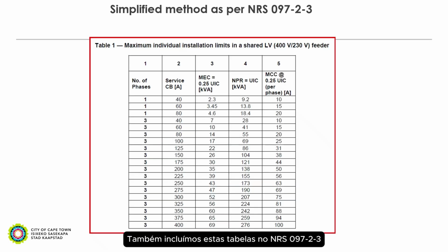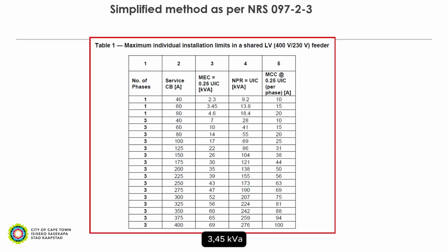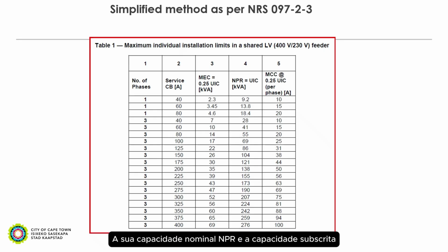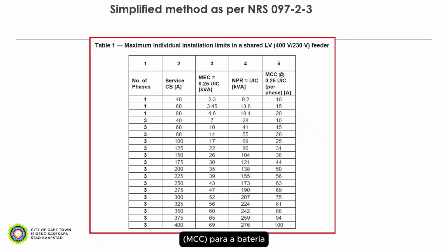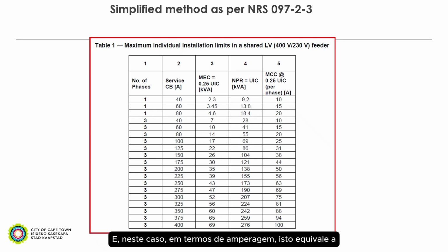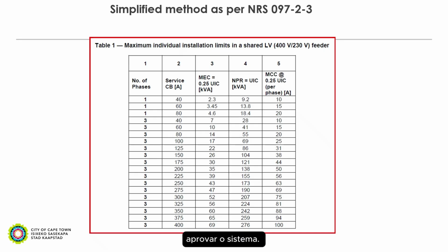We've also put these tables in the NRS 097-2-3 to make it easier. So these are the maximum export capacity for the 25%, for example, for the various circuit breaker sizes, meaning then a customer with a single phase 60 A supply, for example, cannot exceed the maximum export capacity of 3.45 kVA. His NPR nameplate rating and the utility installed capacity will be 13.8 kVA, and the MCC, the maximum charging current for the battery, should be basically 25% of the UIC, and in this case comes to 15 amps. And we can basically use this table to determine if the customer falls within these limits and thereby approve the system.